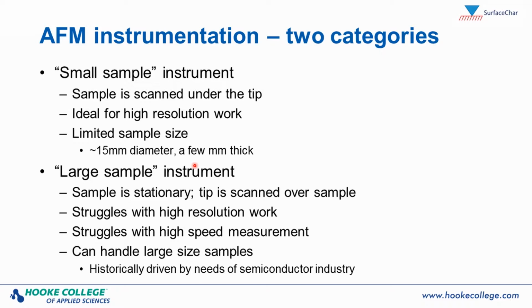For many samples it's great and things can be cut down to that size, but for many samples it's not. So there's a different approach to building AFM equipment, called the large sample instrument, where your sample is stationary and the tip is what is scanned over the sample. Every design has its pros and cons. The con of a large sample instrument is that typically it will struggle with higher resolution work, because the motion and detection are both done by the tip. Whereas on a small sample instrument, the motion is done by the sample and the detection by the tip, which enables better signal to noise ratios. Here the tip is doing all the work, so it can compromise high resolution measurements.